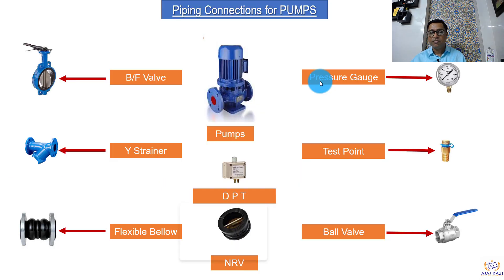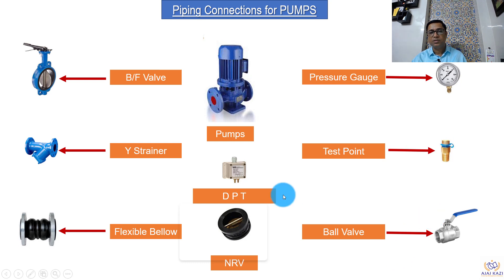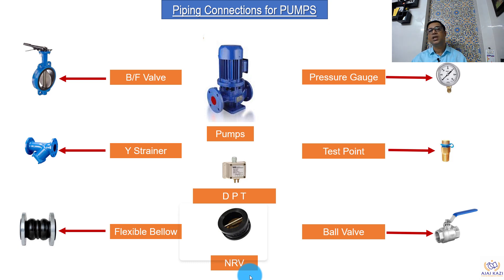In piping connections for pumps, we have many other items that need to be covered. First is the butterfly valve — it looks like that, and I have created some photographs for better visibility and understanding. Then we have a Y-strainer, flexible bellows, the pump itself, pressure gauges, test points, ball valves, differential pressure transmitter, and non-return valves — also called check valves. These are the important elements in any pump piping connection, and I thought I would give you a brief idea of what goes into a pump connection apart from piping.